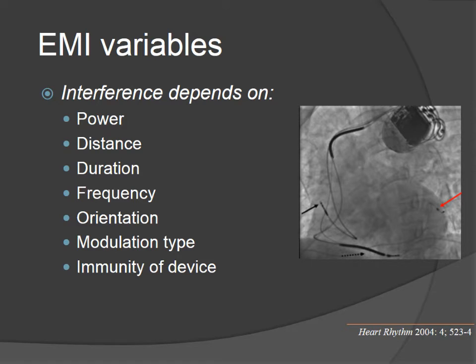What are the variables that play a role? Basically, the power of the source emitting the fields, the distance the field or source is from the implanted device, how long it lasts—so is it a continuous application or a cyclical one? If cyclical, what frequency does it operate at? Then the orientation—think of someone standing under a power line: are they lying down, standing up, sideways—because the field the device feels, especially the area contained by the pacemaker or defibrillator leads, will be affected by that. Then we look at the modulation and the way the field is delivered, and then the immunity of the device itself to all of it.